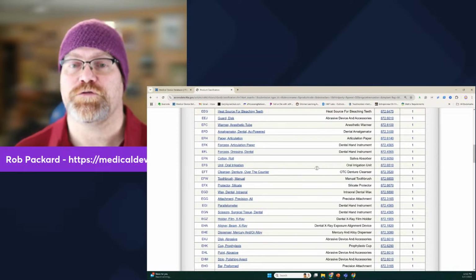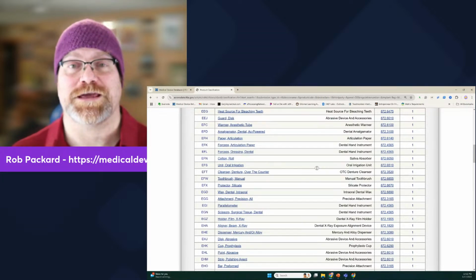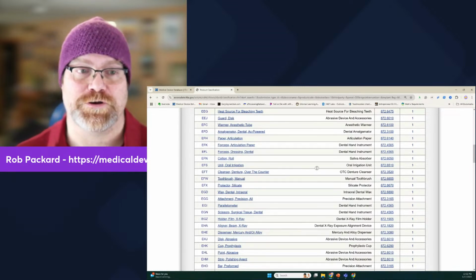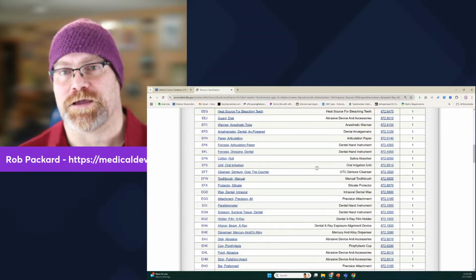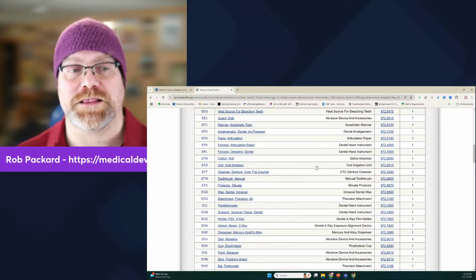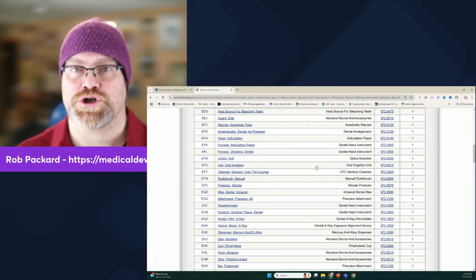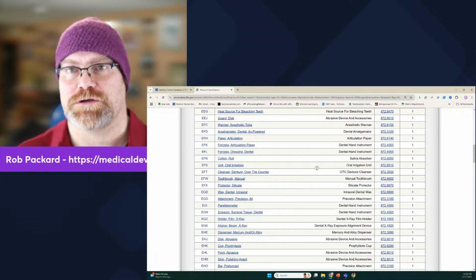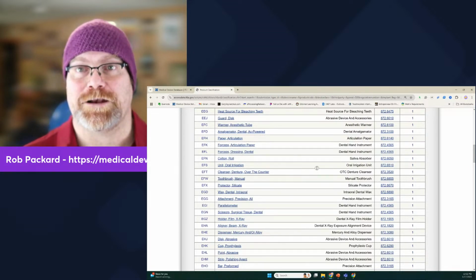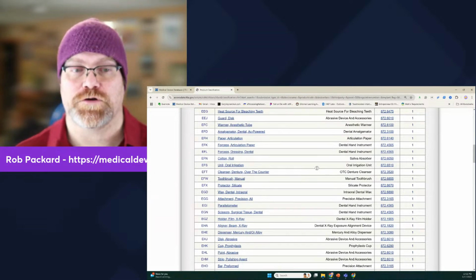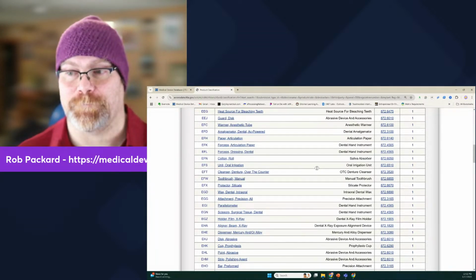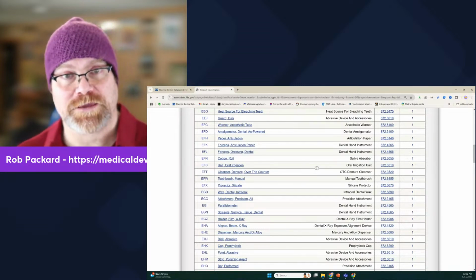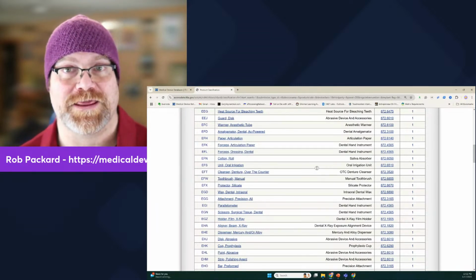So every once in a while, you surprise yourself. And in this case, it was a 1992 510K that had been filed for a similar device. And I think I can use that as a predicate. So every once in a while, you get really lucky in those advanced search terms. A lot of companies will use that advanced search function to look for a way to get around a 510K. They'll look for a class 1 device that's exempt, which is what this was, the dental hand instrument. But in this particular case, I knew I wanted something that was 510K cleared.